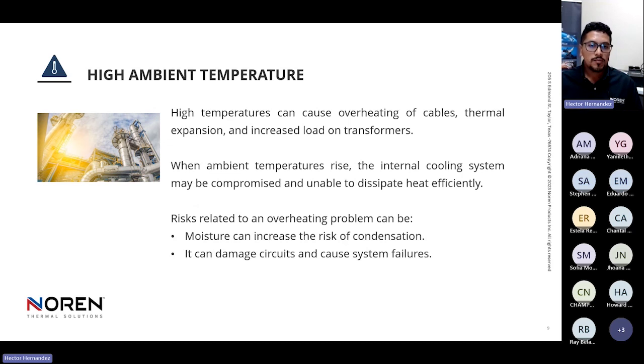Also, high ambient temperatures. With temperatures above 120, 130, or even 140 degrees Fahrenheit, we do not recommend ambient cooling applications like the two fans technology. Because if we are introducing the ambient air into the electrical panel, we are introducing heat inside of our electrical panel, and this will cause overheating. The interior temperature will rise. We can even increase dust and moisture, which will raise the internal temperature even more.